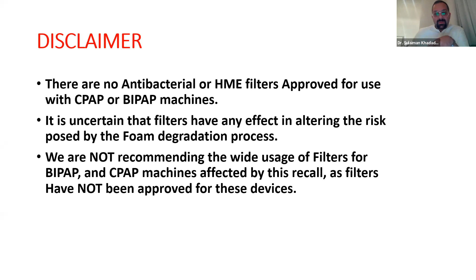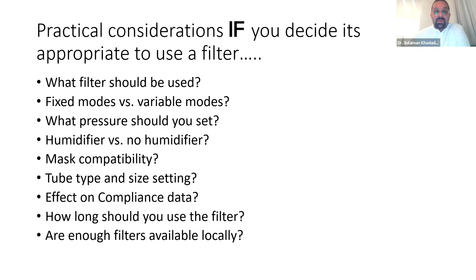And it turns out, actually, there's a lot of practical considerations if you decide to use a filter. For example, what filter should you use? Should you use a regular antibacterial filter, HME filter? Should you use fixed or variable modes? What pressure should you use? A humidifier versus no humidifier? Mask, are all masks compatible? What tube size, heated tube, or what should you use? And actually the effect of this on compliance. And the key question is, how long should you be using these filters? And I think you have to ask yourself always, are there enough filters available locally?